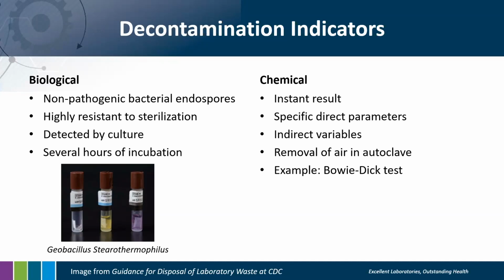And then on the right, you have an example of a biological indicator that passed. It remained purple, and there is no growth. I want to call your attention to these little bars, the black bars and the horizontal bars above the media. On the one on the left, which is unused, you see the black bar, and on top of that, you see the blue horizontal bar. That shows me this has not been, it is just off the box, right? I didn't put it in the autoclave. The one in the center, I know it didn't pass, so it was autoclaved, but it didn't pass.